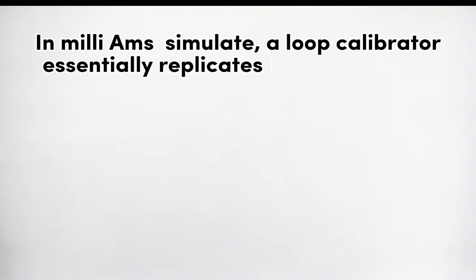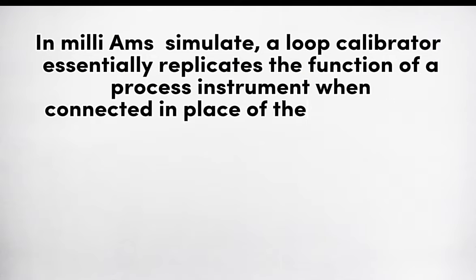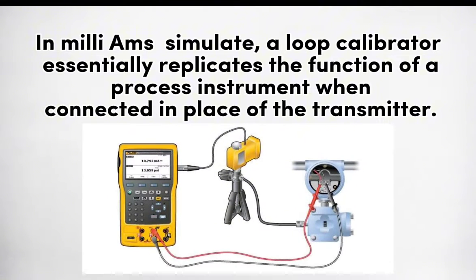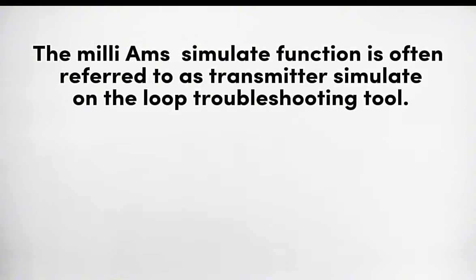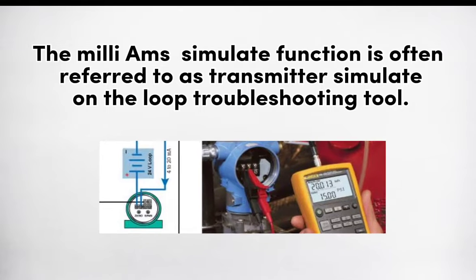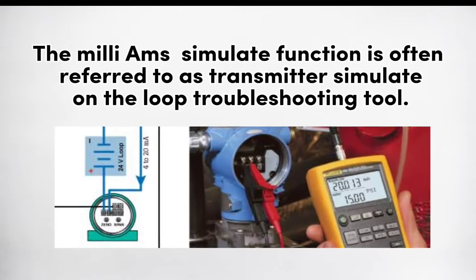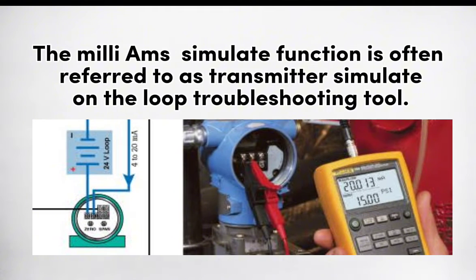In milliamp simulate mode, a loop calibrator essentially replicates the function of a process instrument when connected in place of the transmitter. The milliamp simulate function is often referred to as transmitter simulate on the loop troubleshooting tool.